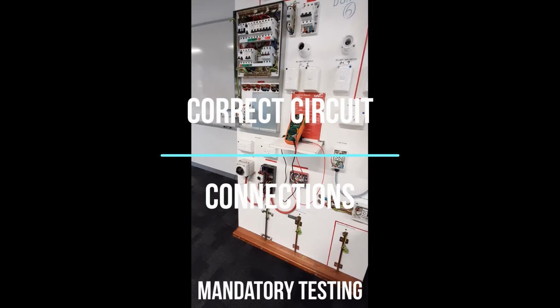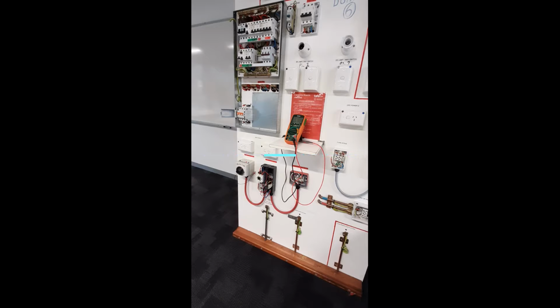This video will demonstrate how to perform the correct circuit connections test of an electrical installation. You will test actives to actives, neutrals to neutrals, and earths to earths. Device and setting.